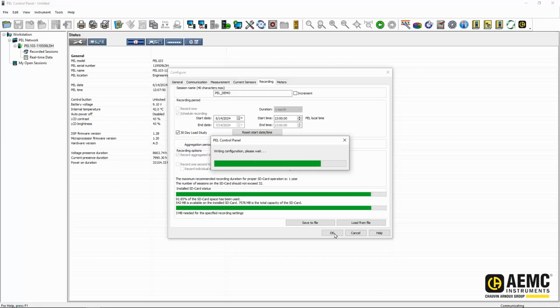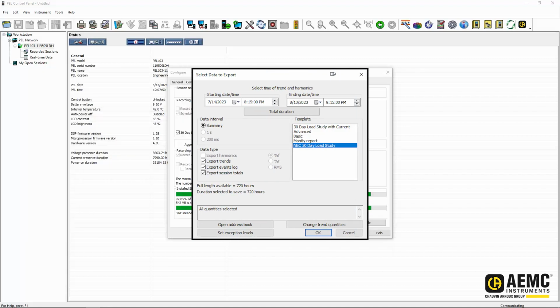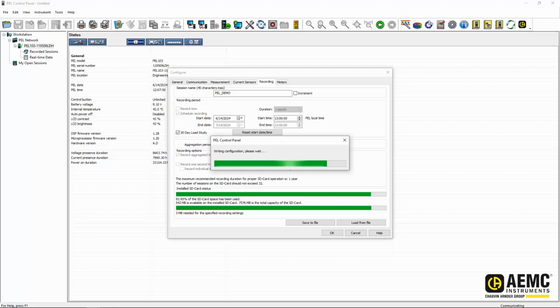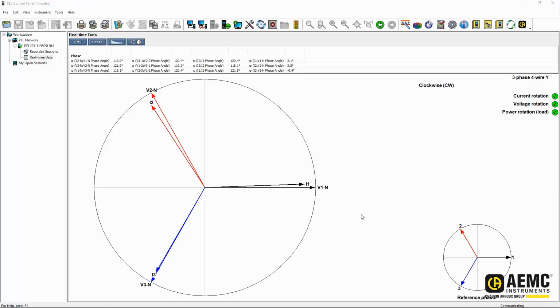Once I've clicked OK, the PEL control panel is going to synchronize the data inside the PEL with the control panel configuration, and I should be ready to start my recording. Note that when I use the 30-day load study function, it selects the next rounded hour to start the recording. The control panel not only displays the instrument status, but also real-time values are displayed. A great control panel feature is the phasor diagram.